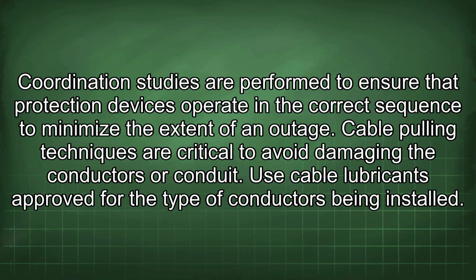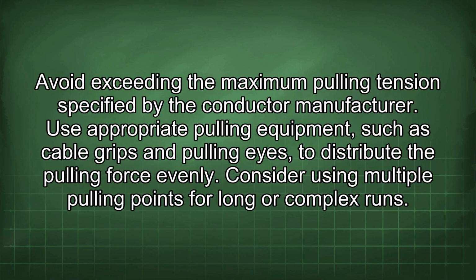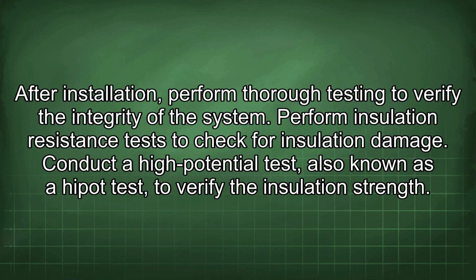Cable pulling techniques are critical to avoid damaging the conductors or conduit. Use cable lubricants approved for the type of conductors being installed. Avoid exceeding the maximum pulling tension specified by the conductor manufacturer. Use appropriate pulling equipment, such as cable grips and pulling eyes, to distribute the pulling force evenly. Consider using multiple pulling points for long or complex runs. After installation, perform thorough testing to verify the integrity of the system. Perform insulation resistance tests to check for insulation damage.